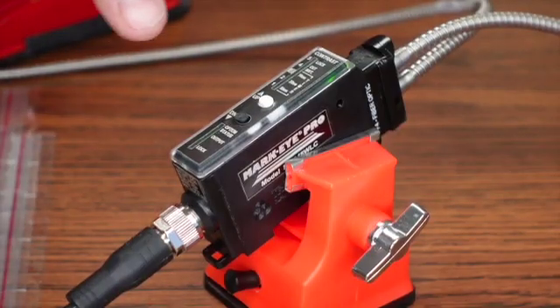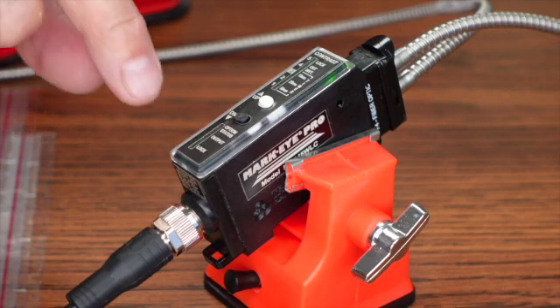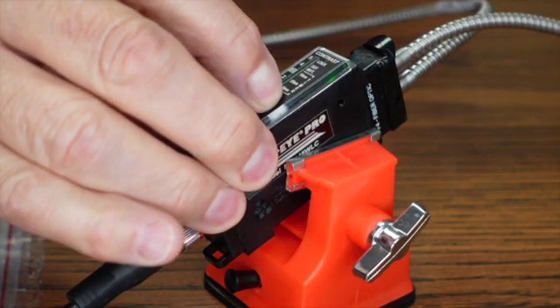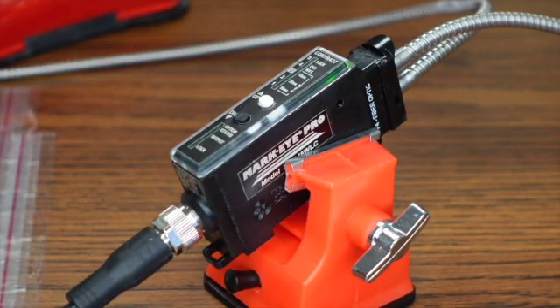This is the Mark-Eye Pro registration mark sensor, model MEP45 WLCF4. It has a white light LED. To set up the sensor, all you do is hold down this white button for two seconds and it's set up. You can then tweak it by just tapping the up or down button depending on the application.